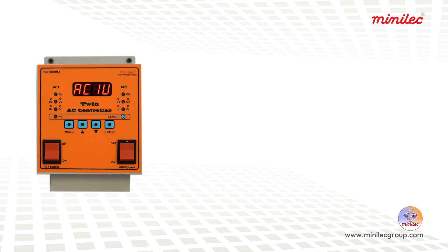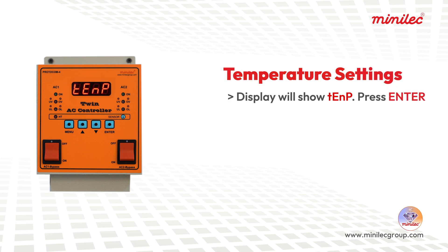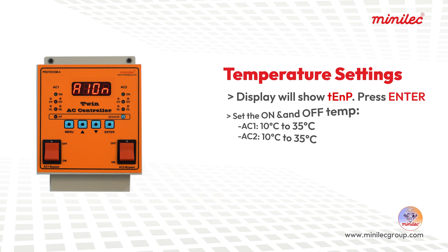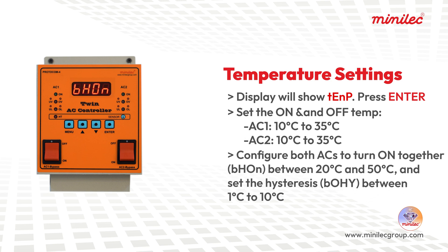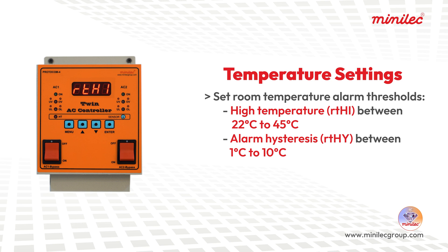Temperature settings: When the display shows TEMP, press ENTER. Set the ON and OFF temperatures for each AC: AC1 between 10°C to 35°C, AC2 between 10°C to 35°C. Configure both ACs to turn on together between 20°C to 50°C, and set the hysteresis between 1°C to 10°C. Set room temperature alarm thresholds — high temperature (RTHI) between 22°C to 45°C, and alarm hysteresis (RTHY) between 1°C to 10°C.